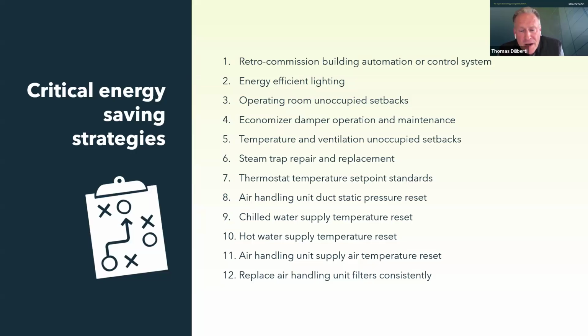So temperature and ventilation, unoccupied setbacks, we talked about that with the operating room, but the idea is let's change the temperature, let's change the ventilation rates, let's do it all over the place if the opportunity arises. Number six, steam trap repair and replacement.